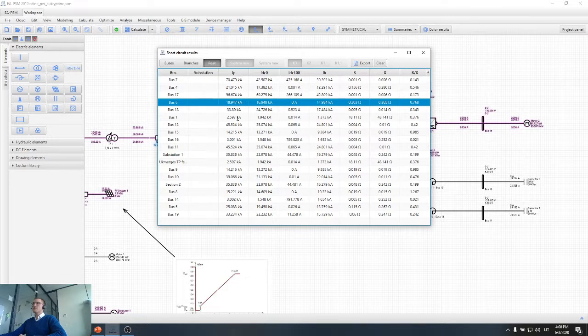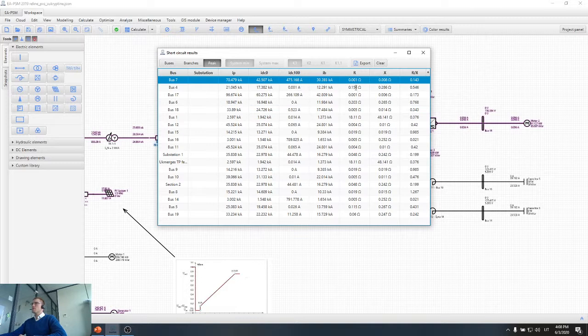So these DC components of the short circuit current are calculated in the worst case scenario, and the methodology for calculating these currents uses resistance and reactance of the network, which is automatically calculated from the data provided by the user. So DC components actually can be calculated.